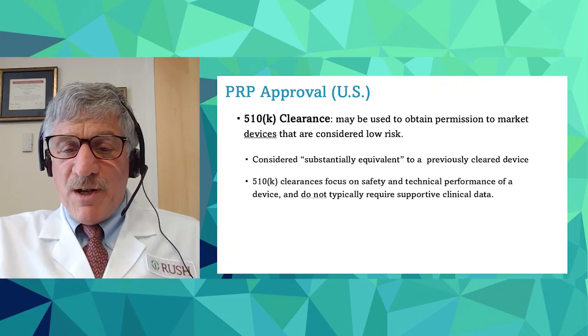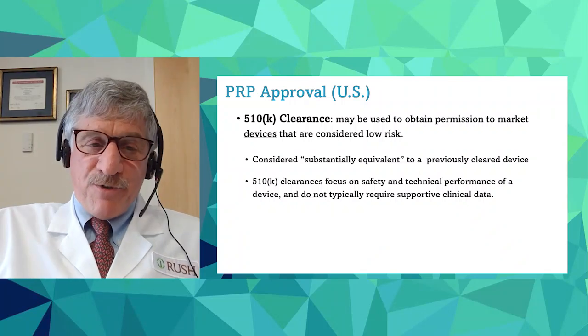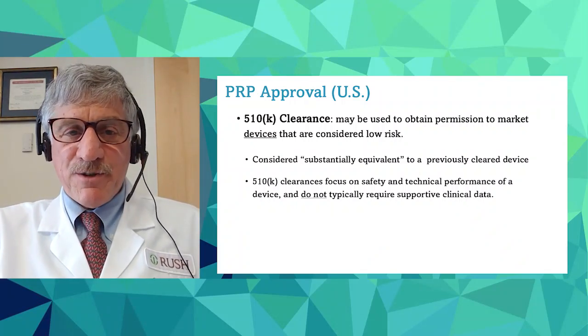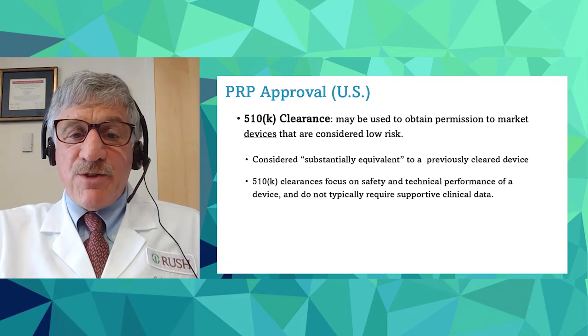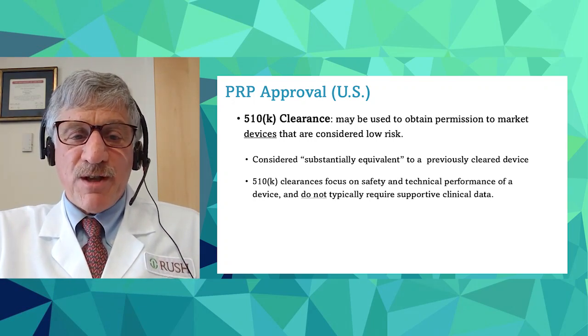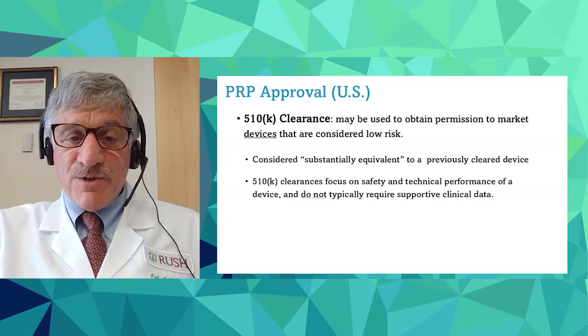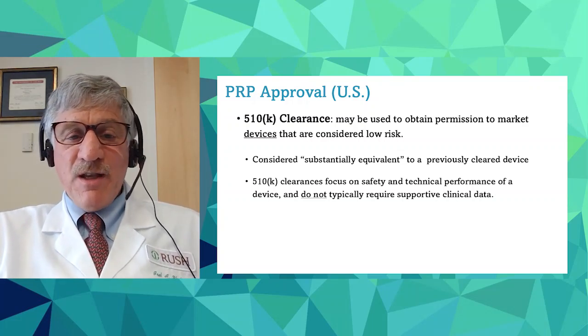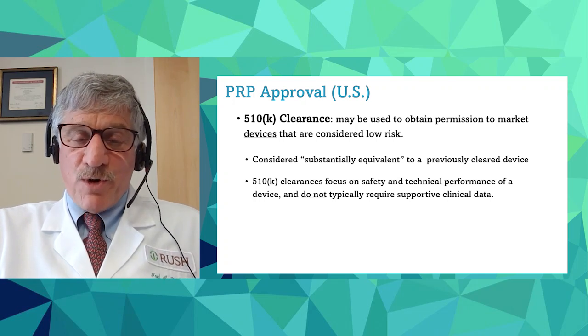However, it never needed to be proven to be effective for any of these because it received what's called 510K clearance by the US FDA. This is used to obtain permission to market devices that are considered low risk. 510K clearances focus on the safety and the technical performance of the device, and they don't require supportive clinical data.